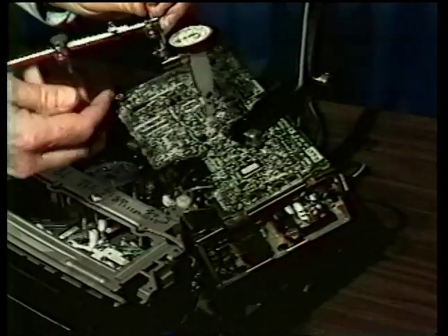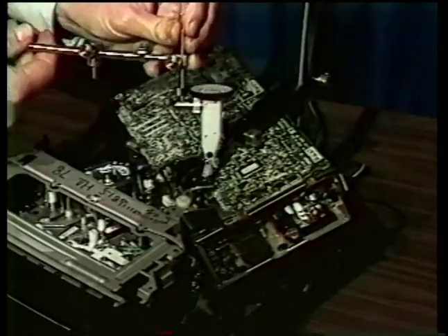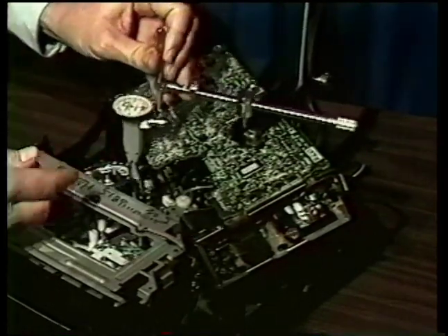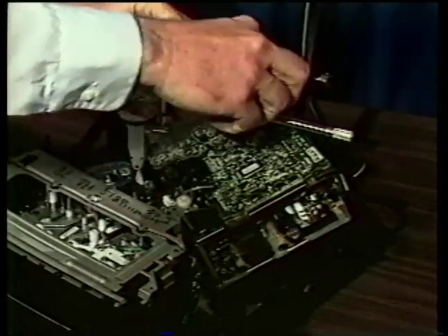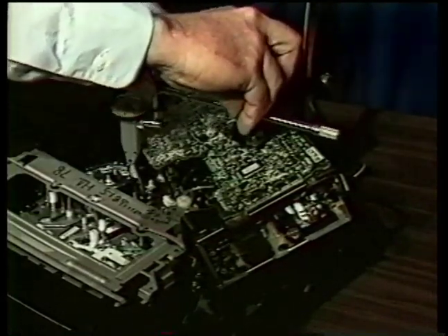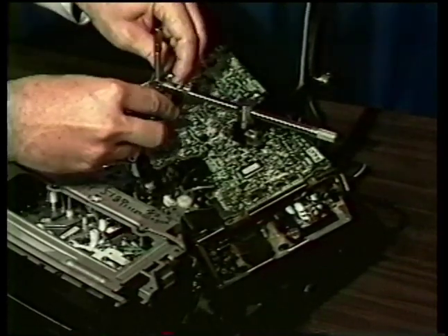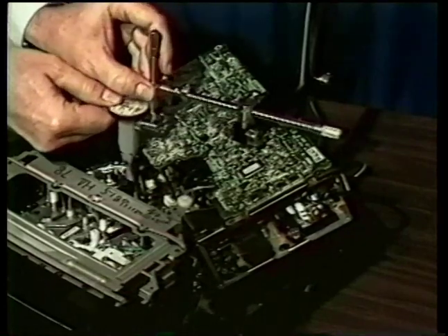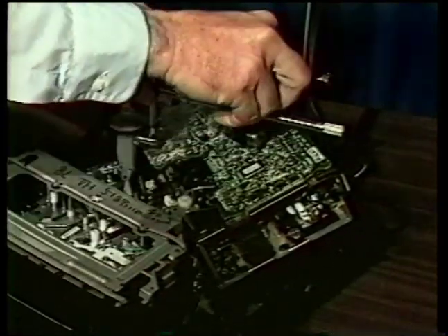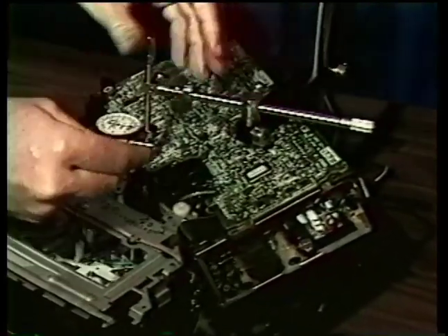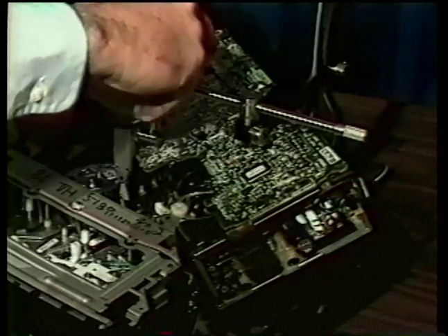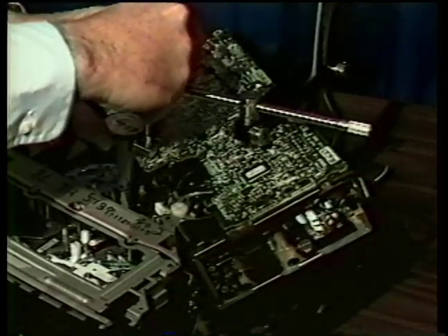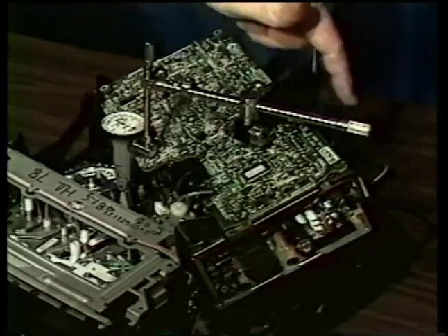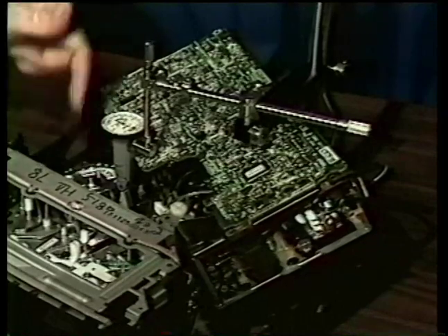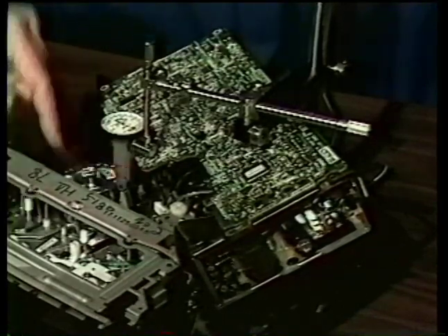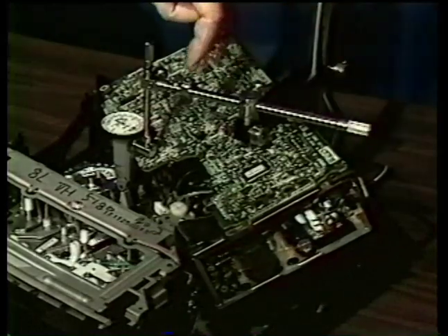So I've loosened the horizontal coarse adjustment and the vertical coarse adjustment knobs to allow me to actually place this into the horizontal arm and then position in a coarse adjustment the gauge, the indicator, over to the actual video drum. Okay, I'm aiming, this is fairly important, I'm aiming the horizontal arm basically at the center of the drum as close as I can and still getting around the printed circuit board. So I'm going to be using the horizontal adjustment here to actually engage the tip against the drum later.